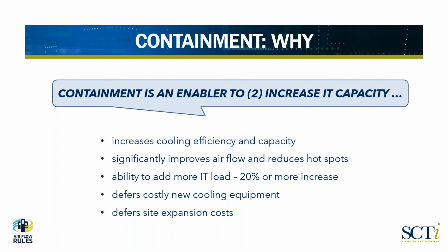Arnold, one of the things that Polargy experienced, a conversation I would hear time and time again, was the data center manager would come to us and say, I have enough UPS capacity, but I just can't get any more equipment into the room because I can't keep it cool. I believe this capacity question was the catalyst for at least 50% of containment projects, versus just saving energy. Saving energy was nice, but often folks couldn't put any more equipment into the room, even though they knew they had the cooling capacity and the UPS capacity. So I'm going to say that maybe 50% of the time over the last 10 years that we did a retrofit project, it was because of the capacity issue, not the energy savings.